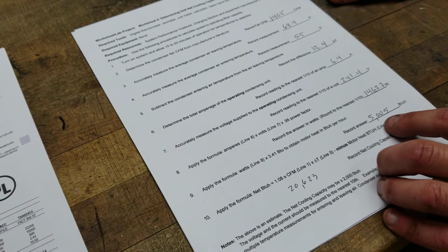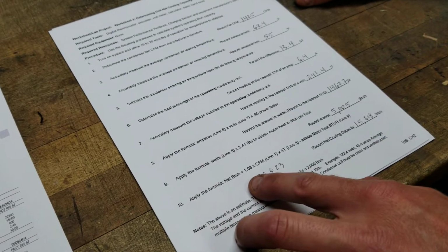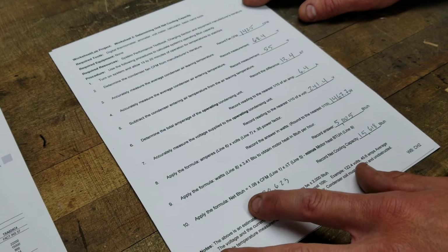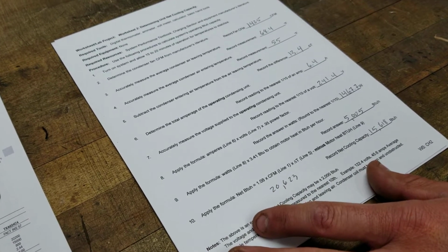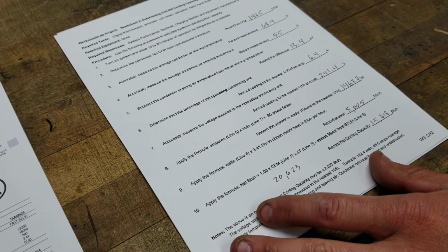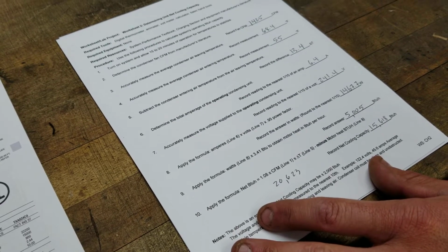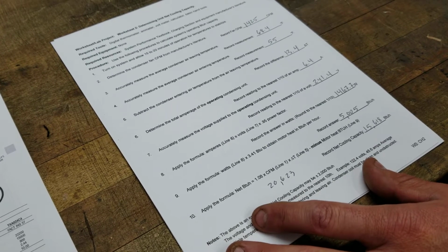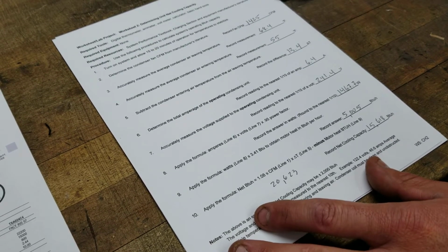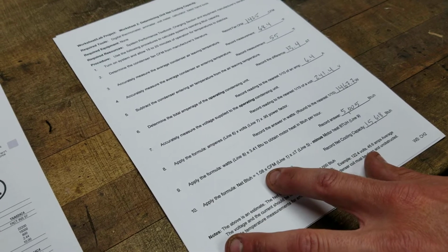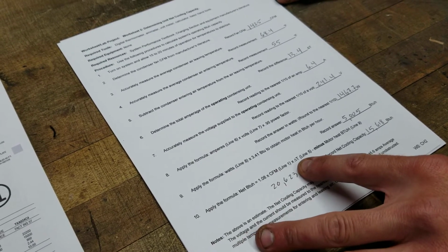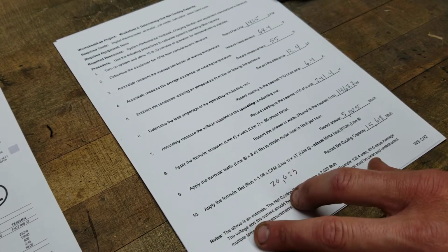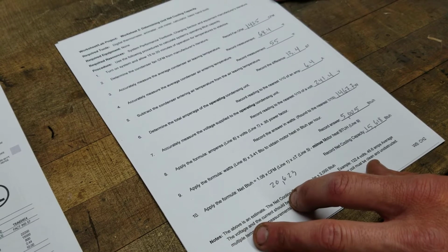Okay? So we're going to apply the following formula. You guys all know this, the sensible heat formula. Everything we're doing with the condensing unit is all sensible heat. We're not changing the humidity at all. We're just rejecting all the sensible and latent heat from the evaporator. We're rejecting it all sensible into the atmosphere in the ambient conditions. So we're going to use the 1.08 times CFM times delta T. 1.08 is always a constant. That's our specific heat BTU.